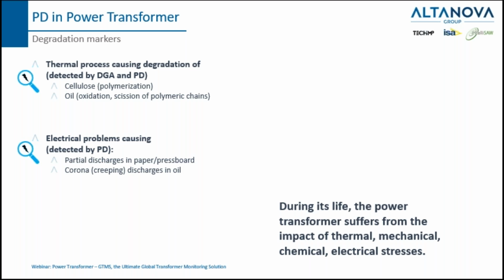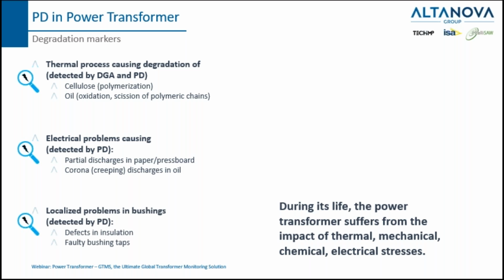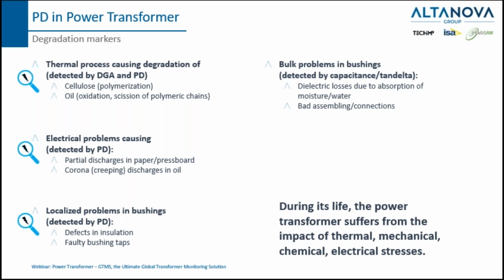or other discharges in oil, and these can be detected by partial discharge. Even localized problems in the bushing, like defects in the insulation or faulty bushing taps, can be detected. In case of bulk problems in the bushing, dielectric losses due to, for example, moisture or water or bad assembling are normally detected by the tan delta system.